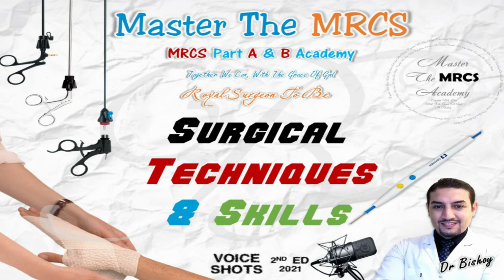This may result from careless handling of the devices, or in the case of the monopolar devices, forgetting to apply a return electrode plate. In this situation, the patient may develop a contact burn when electricity flows to the earth. So take care. If you smell meat burning inside the operating room, they are not doing a barbecue in the operating room. It's prohibited. So most probably it's a barbecue of your patient.